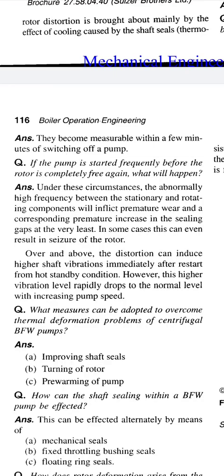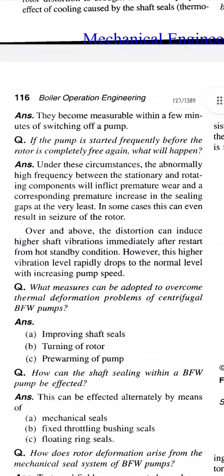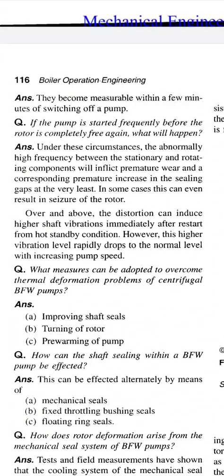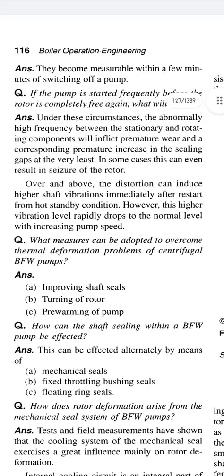In some cases, this may even result in seizure of the rotor. Over and above this, the distortion can induce higher shaft vibration immediately after restart from hot standby conditions. However, this higher vibration level rapidly drops to the normal level with increasing pump speed.